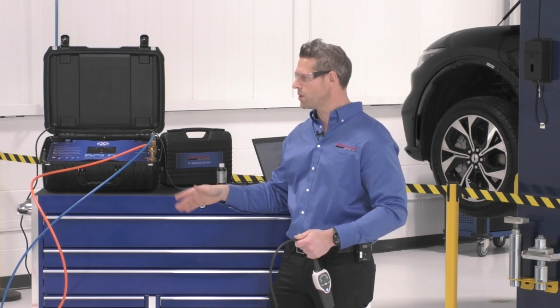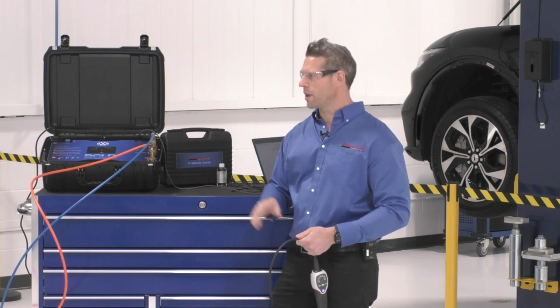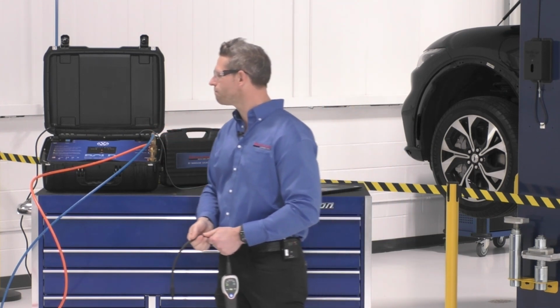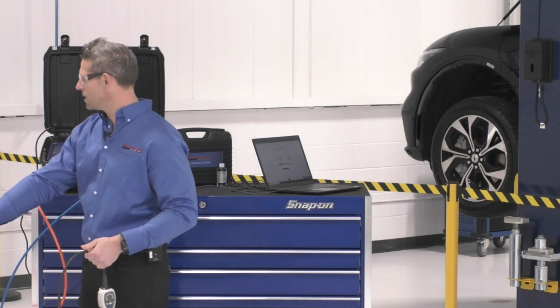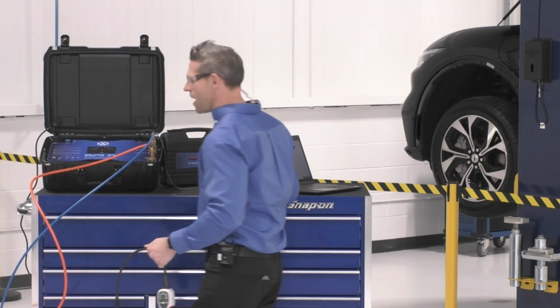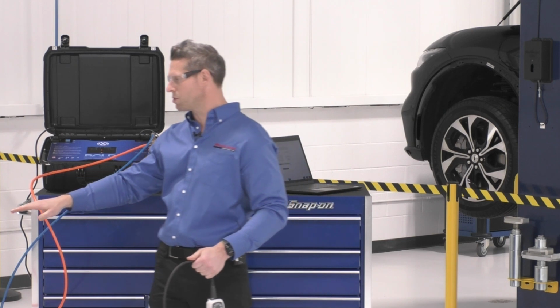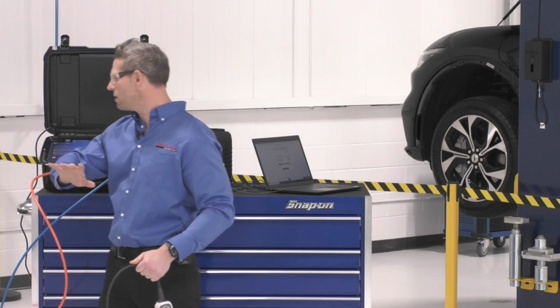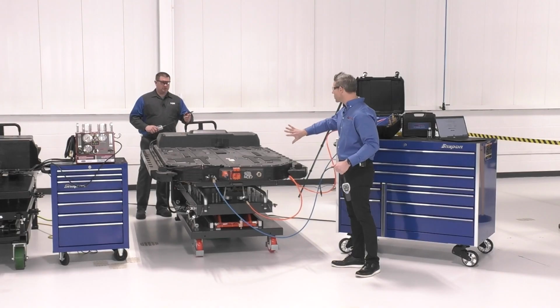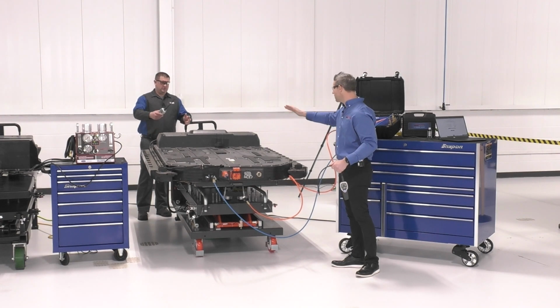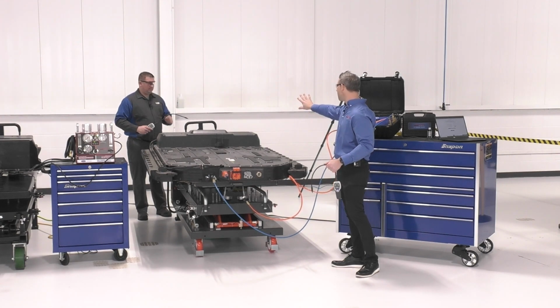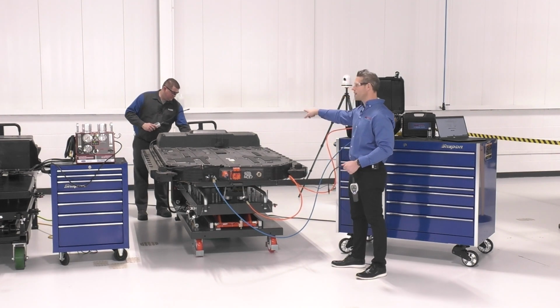It works great for these batteries too—it's clean, no residue, unlike using a vapor or soapy water spray for leaks. So what we're using is half a PSI, which is what this enclosure is rated for. We're injecting the nano gas, and we want to make sure it's homogeneous inside, proliferating all the way to the back of the battery where there's a connector.